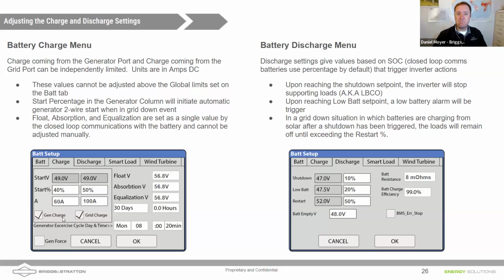Daniel, is AC or DC amperage being displayed there? DC. Yes, this is from the perspective of the battery, and the battery is DC. So when we say 60 amps of DC charging, that's 60 amps at 50 volts, only about 3,000 watts. And when we say 100 amps from the grid port here, we're talking about 100 amps DC at approximately 50 volts, so it's about 5,000 watts there. So keep those in mind. These are DC amperages. I got that question again this morning. That call came in about that: are these AC or DC? And these are DC amperages. This is from the perspective of the battery.